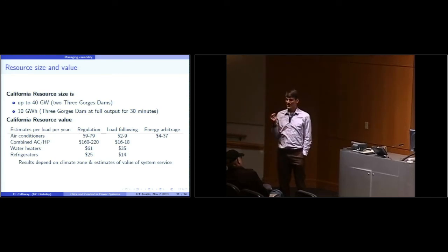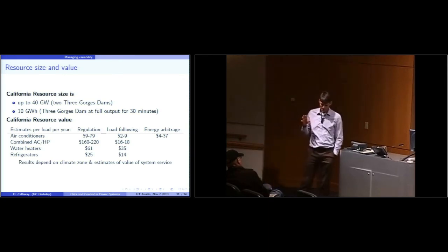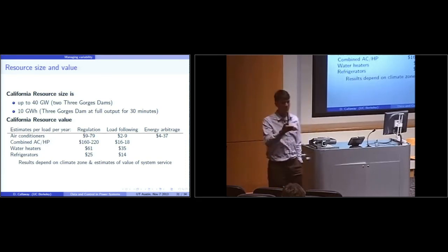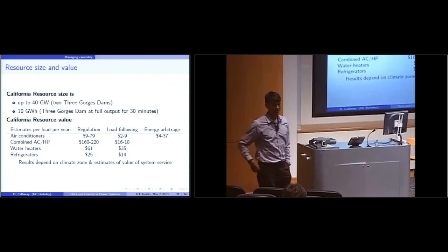So I got confused about this, and I'm probably not telling you anything you don't already know, but when I first started learning about frequency regulation and 4-second timescale commands, I thought that's pretty high performance standards. But just because the command arrives every 4 seconds, that doesn't mean that the resource is actually able to, or even required to, do exactly what it's being told every 4 seconds. So I think it would be tolerable if the communication system had some delay or some dropped packets.